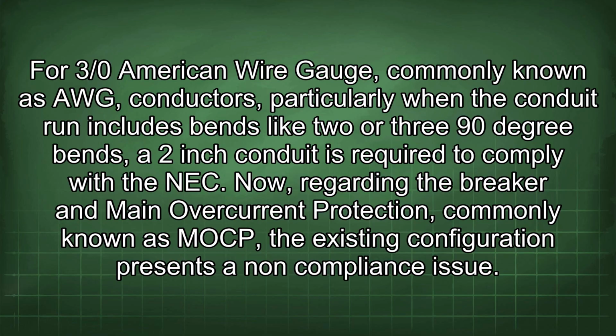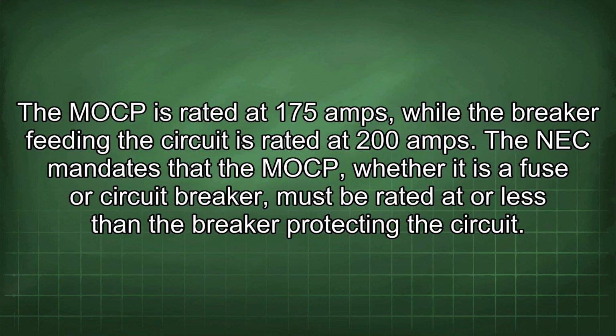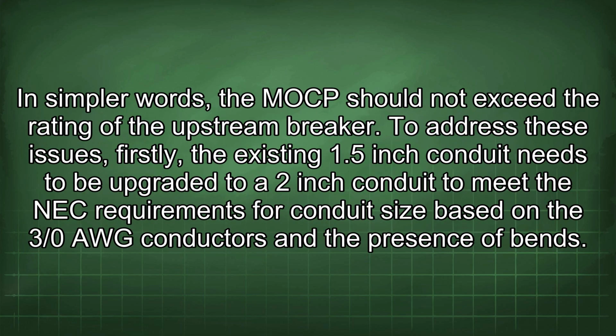Now, regarding the breaker and main overcurrent protection, commonly known as MOCP, the existing configuration presents a non-compliance issue. The MOCP is rated at 175 amps, while the breaker feeding the circuit is rated at 200 amps. The NEC mandates that the MOCP, whether it is a fuse or circuit breaker, must be rated at or less than the breaker protecting the circuit. In simpler words, the MOCP should not exceed the rating of the upstream breaker.